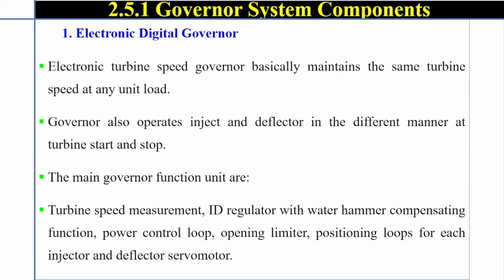Governor system components. The first one is the electronic digital governor. Electronic turbine speed governor basically maintains the same turbine speed at any unit load. Governor also operates injector and deflector in a different manner at turbine start and stop. The main governor function units are turbine speed measurement, PID regulator with water hammer compensating function, power control loop, opening limiter, positioning loops for each injector and deflector servo motor.